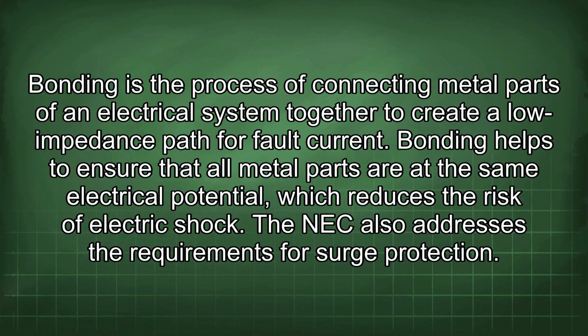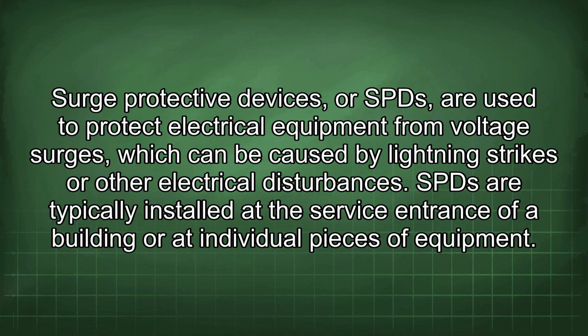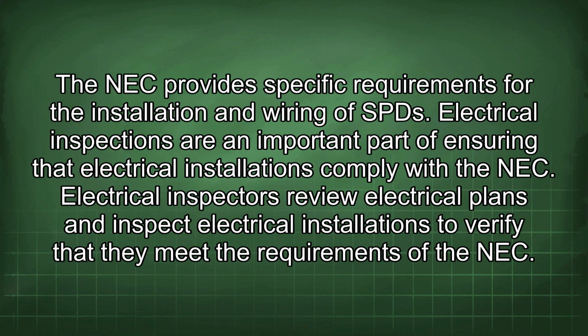The NEC also addresses the requirements for surge protection. Surge protective devices, or SPDs, are used to protect electrical equipment from voltage surges, which can be caused by lightning strikes or other electrical disturbances. SPDs are typically installed at the service entrance of a building or at individual pieces of equipment. The NEC provides specific requirements for the installation and wiring of SPDs.